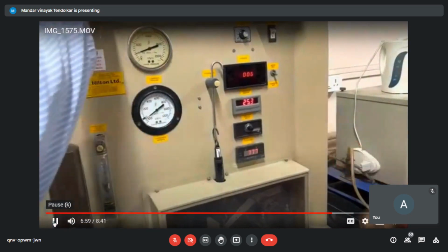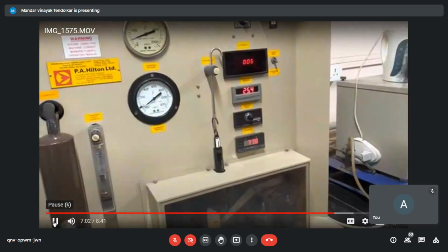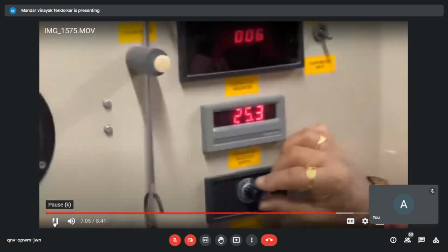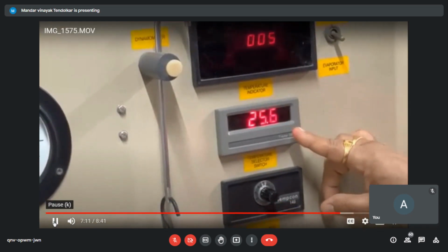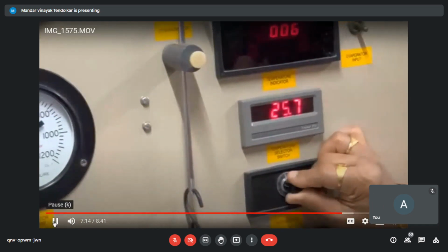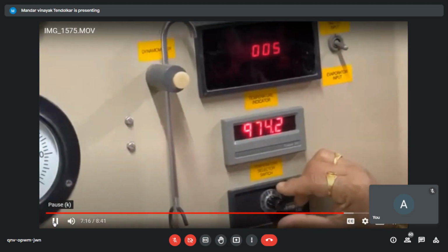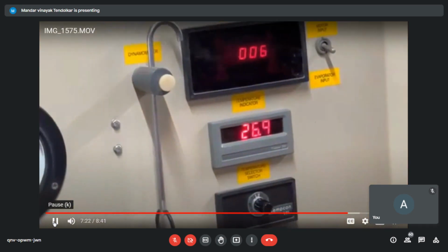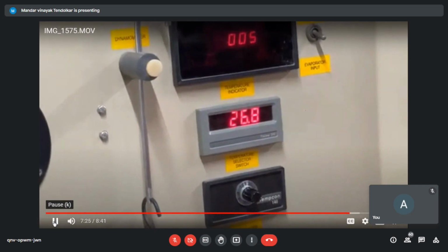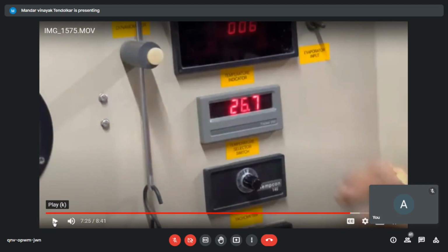Okay, let us start the video again. So temperature further reduces. 25 and then again coming back to 27 or 28. This is your water inlet, cooling water, 25. So 25 is your inlet condition and 27 or whatever it is, 28, that is the exit condition. It is a cooling water, so naturally water gets heated, refrigerant gets cooled. So 25, let's say, is your water inlet, goes to 27, heating, correct?